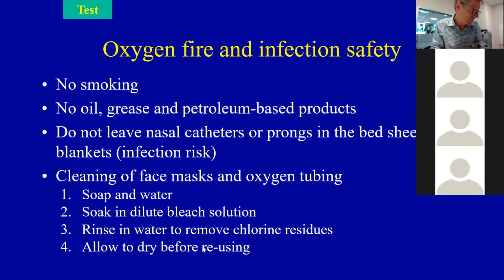I think you guys know how to clean oxygen equipment and are really conscious of infection control procedures, but it is important. Now we'll just check our concentrator and see what we're up to. Okay, so this concentrator has made, can you see what it is? Oh, 95%. Yeah. So a well-functioning, properly functioning oxygen concentrator will make about 95% oxygen. All right, and the reason to use the oxygen analyzer is to detect problems early, because if the concentrator is not making 85% oxygen, then we need to be identifying that early and trying to troubleshoot and making sure that we are doing all the right things in terms of keeping it clean and dry, etc.